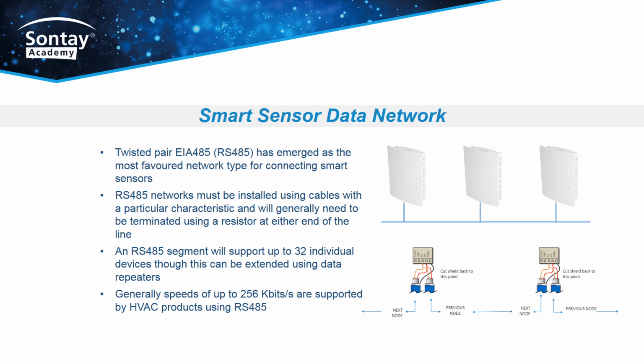EIA485, or as it is more commonly known, RS485 twisted pair networking, is a well-established technology. The 2-wire variant of this is used in many different devices to carry data using both open and closed protocols. It is important to use the correct shielded twisted pair cable and to install it properly with screens connected to a potential earth at one end of the cable only. It is generally necessary to then terminate each end of the cable with a 120 ohm resistor to prevent data reflections, which will cause anomalous readings and interference. Maximum bus length is dependent upon the baud rate, but at speeds of up to 90 kilobits per second, 1200 metres should be achievable.